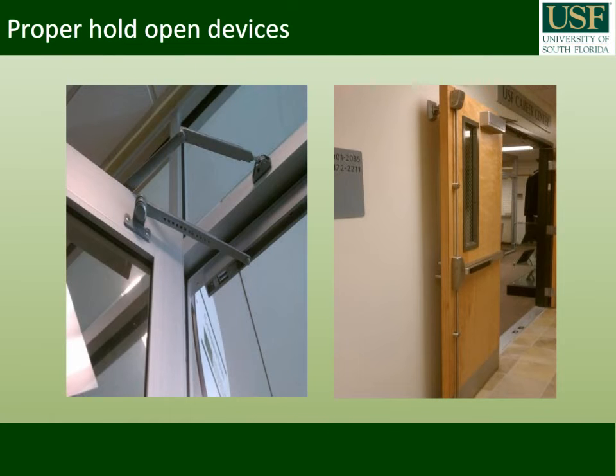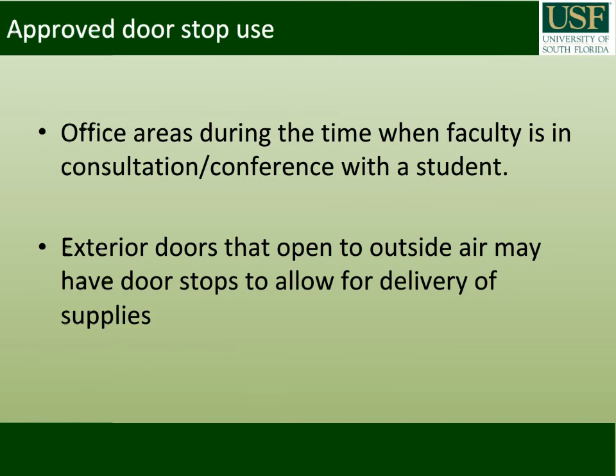Here are examples of two different types of approved hold-open devices for fire doors. There are two instances when door stops can be used. One being in an office area during the time when faculty is in consultation with a student. And the other being when the exterior doors that open to the outside air may have door stops to allow for delivery of supplies.